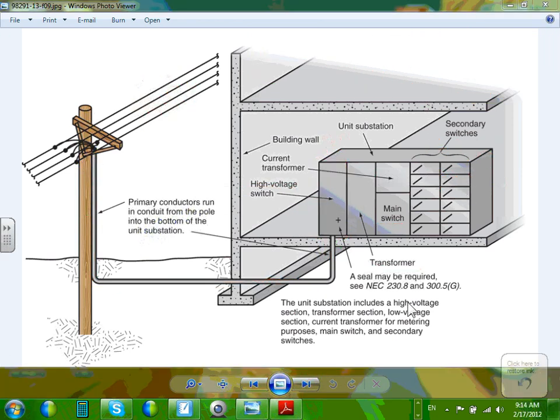Or the utility might ask you to put the conduits for them because you're going to interface. Just put the conduits up to the pole. They'll take it from this point up, the conduit. And then they come and they pull their conductors in the conduit. Can I just get you to understand? We'll talk about service point in a second here. Service point is the point where your responsibility starts and the electrical utility responsibility stops, and vice versa.